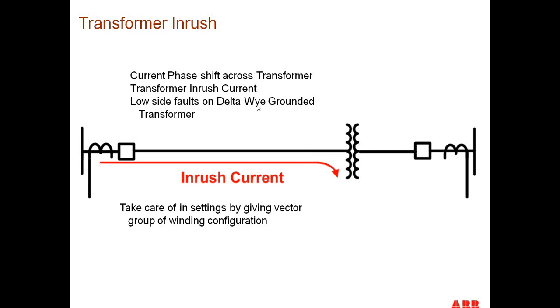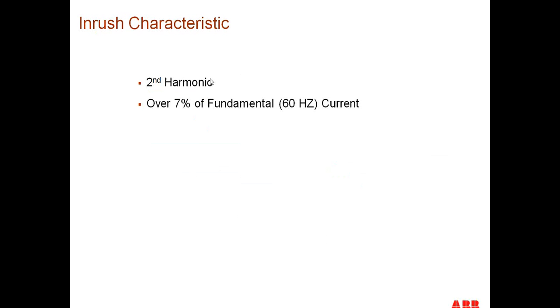Also, with our numerical technology, for a delta-wye transformer, we can shift the currents internally in the relay. We can just tell the relay that we have a delta-wye transformer here, and it will shift the currents on the secondary so that numerically the currents are in phase on both sides of the transformer, so we can do the differential calculation without any errors. So the last thing I need to worry about would be low side faults on the transformer. I just talked about that. So we'd use a second harmonic restraint element: if ever we have second harmonic current above 7% of the fundamental 60 hertz current, then we would block the relay from operating.